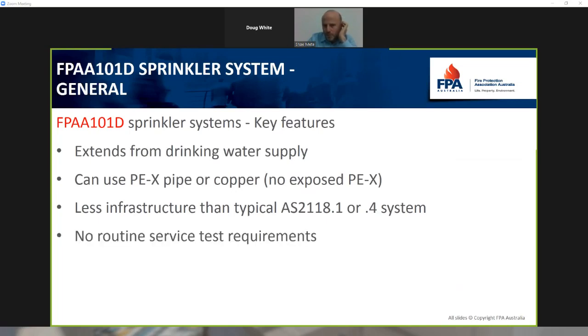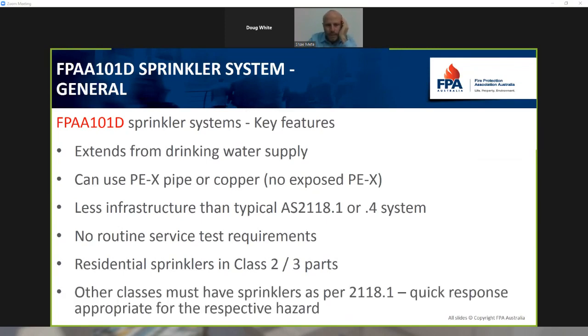No routine service test requirements. There is a requirement to do a survey, just a general inspection, but there is nothing to test. The residential sprinklers are required in Class 2 and 3 parts, so I'm sure Doug will talk to that a little bit later, but we can't be using commercial sprinklers in the SOUs. They must be residential and watermarked residential sprinklers. Other classes are to be, the sprinklers are to be installed in accordance with the requirements of 2118.1, so certainly quick response and for the hazard.